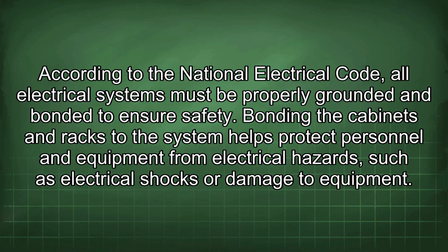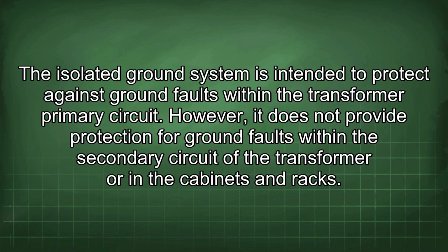According to the National Electrical Code, all electrical systems must be properly grounded and bonded to ensure safety. Bonding the cabinets and racks to the system helps protect personnel and equipment from electrical hazards, such as electrical shocks or damage to equipment. The isolated ground system is intended to protect against ground faults within the transformer primary circuit.